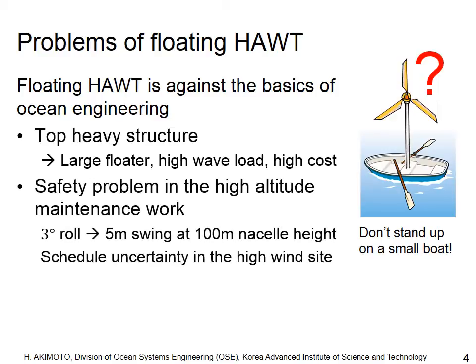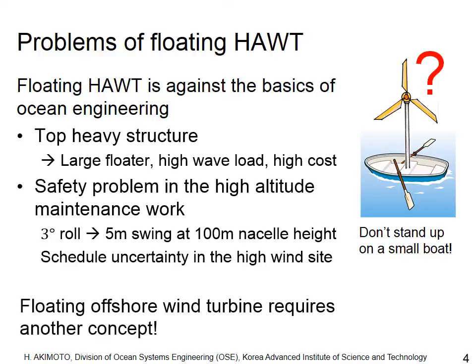The top-heavy structure experiences high wave loads and increases the cost of the device. Also, maintenance work in the high-altitude nacelle is not easy in offshore conditions. Three degrees of tilt of the wind turbine leads to a 5-meter swing inside the nacelle. Because we expect high winds at offshore wind farm sites, there will be uncertainty in maintenance work scheduling, which increases the cost of the project.